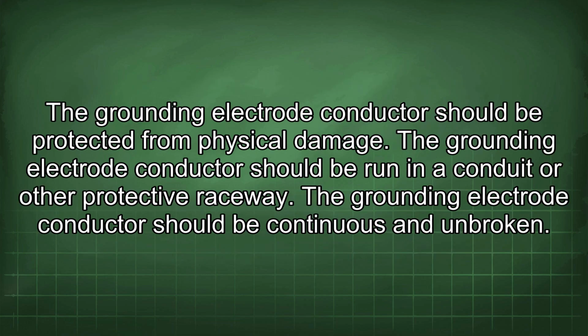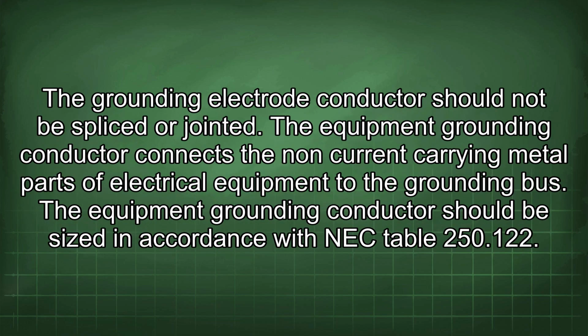The grounding electrode conductor should be protected from physical damage. The grounding electrode conductor should be run in a conduit or other protective raceway. The grounding electrode conductor should be continuous and unbroken. The grounding electrode conductor should not be spliced or jointed.